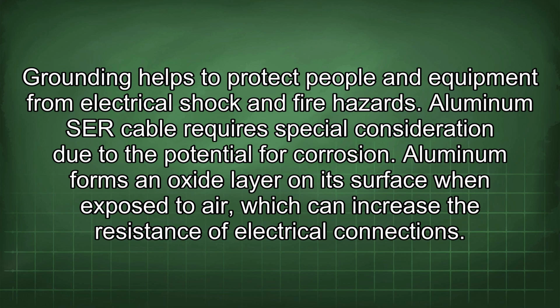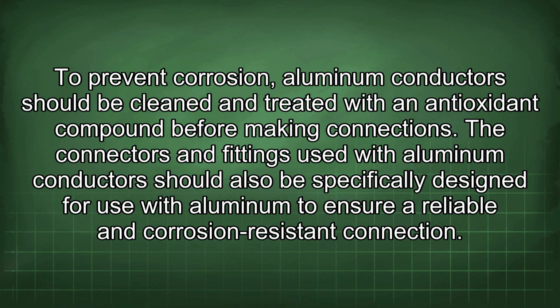Aluminum SER cable requires special consideration due to the potential for corrosion. Aluminum forms an oxide layer on its surface when exposed to air, which can increase the resistance of electrical connections. To prevent corrosion, aluminum conductors should be cleaned and treated with an antioxidant compound before making connections. The connectors and fittings used with aluminum conductors should also be specifically designed for use with aluminum to ensure a reliable and corrosion-resistant connection.